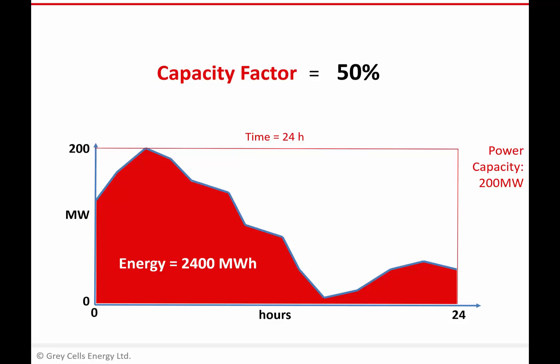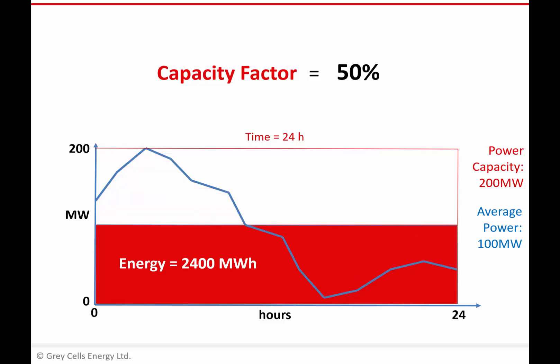The actual energy generated is half of the theoretical maximum you could generate were the plant to operate at full capacity for the full period. We also know the average power is 100 megawatts — the same area as the irregular shape under the actual power curve would be produced by operating the wind farm continuously at 100 megawatts for 24 hours. This means another way to define capacity factor is: average power divided by the maximum power, or installed capacity, of the power plant.